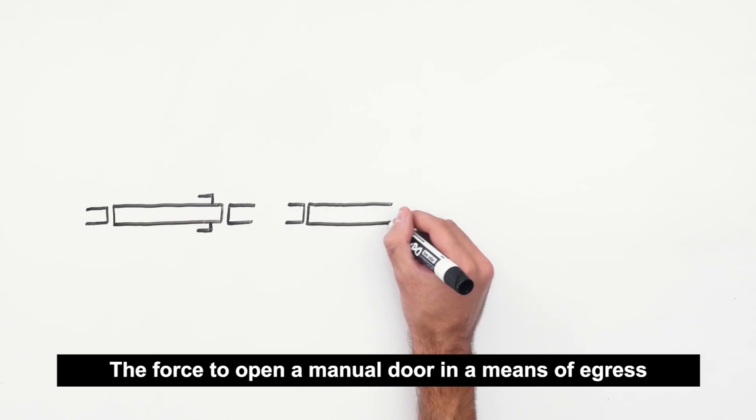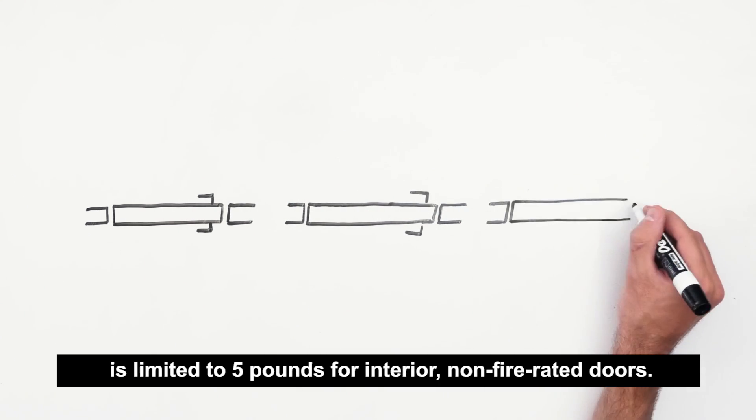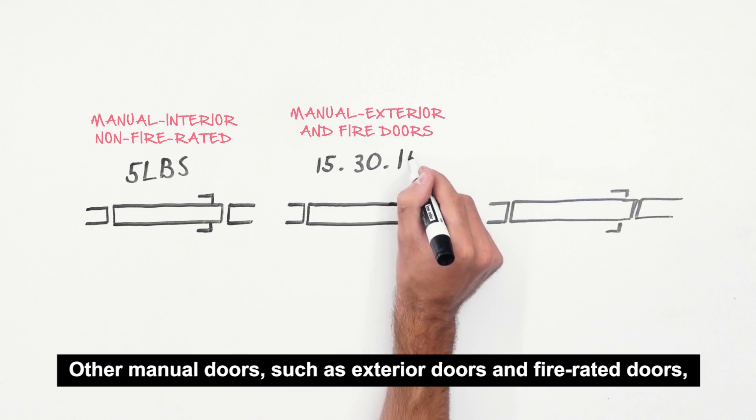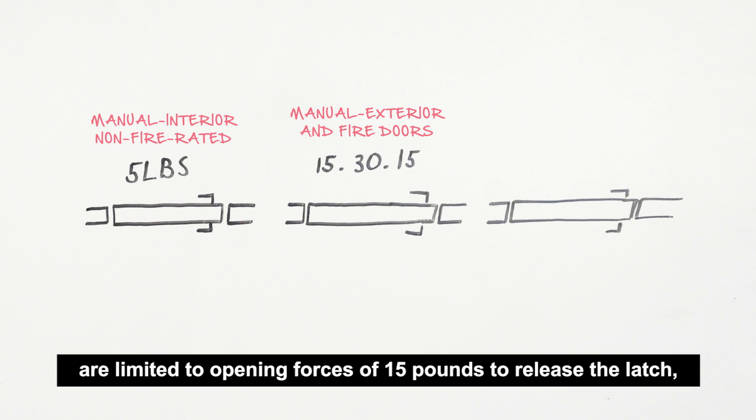The force to open a manual door in a means of egress is limited to 5 pounds for interior, non-fire rated doors. Other manual doors, such as exterior doors and fire rated doors, are limited to opening forces of 15 pounds to release the latch, 30 pounds to set the door in motion, and 15 pounds to swing the door to a fully open position.